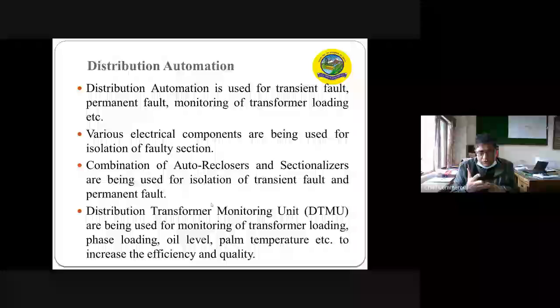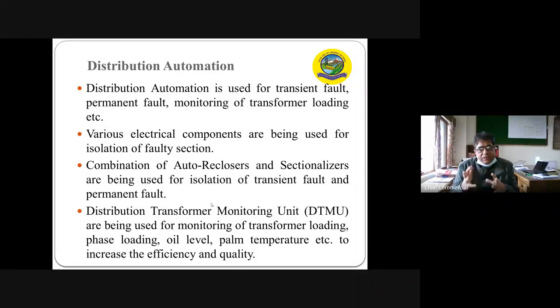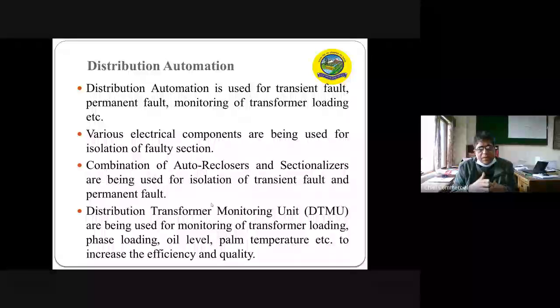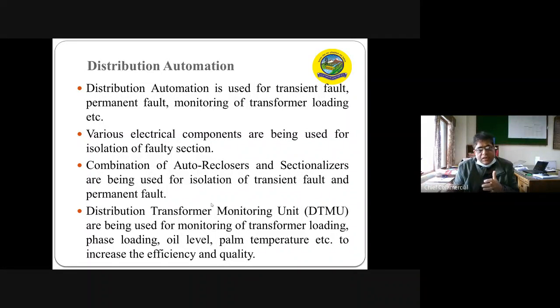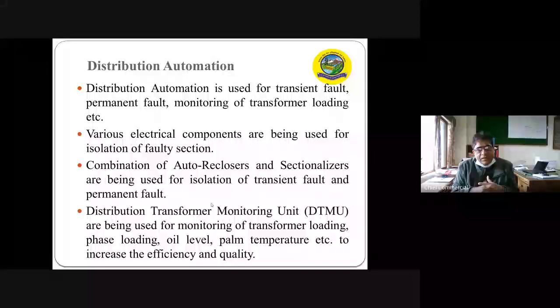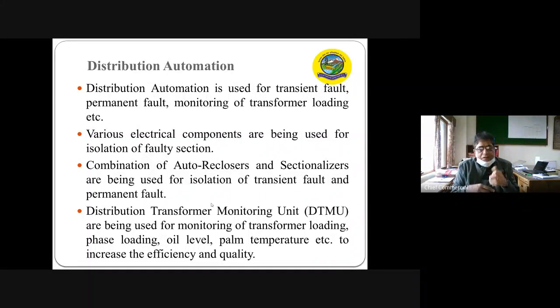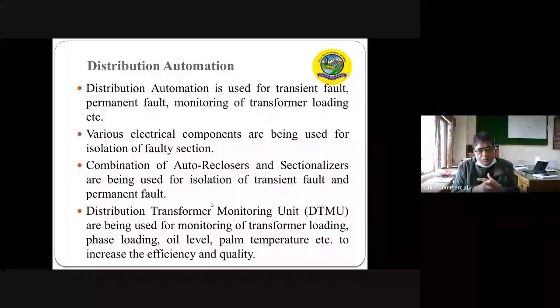So we use the auto reclosers and the sectionalizers. They sense temporary faults and immediately isolate the faulty portion. And again, they give another try. If the fault is cleared, which happens in the case of a transient fault, the system is restored. Without manual intervention, this happens automatically, and it is monitored at the central console center. In case the fault is permanent, the system gets locked out and it sectionalizes, isolating the entire area, and then whenever our crew rectifies the problem, the system is restored again through remote centers.